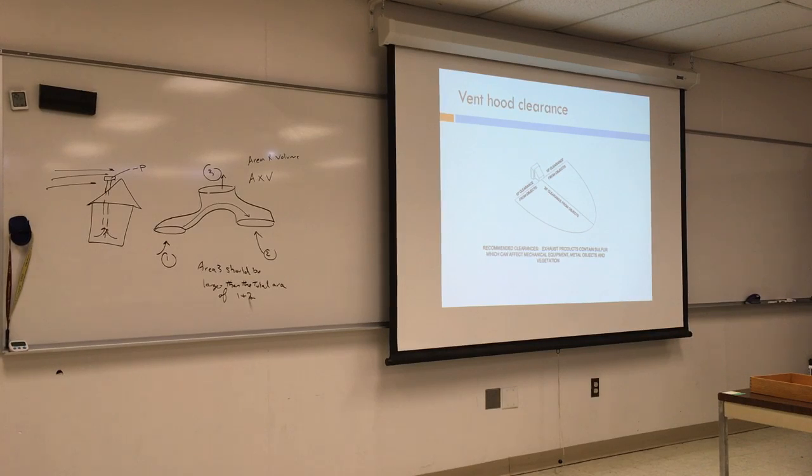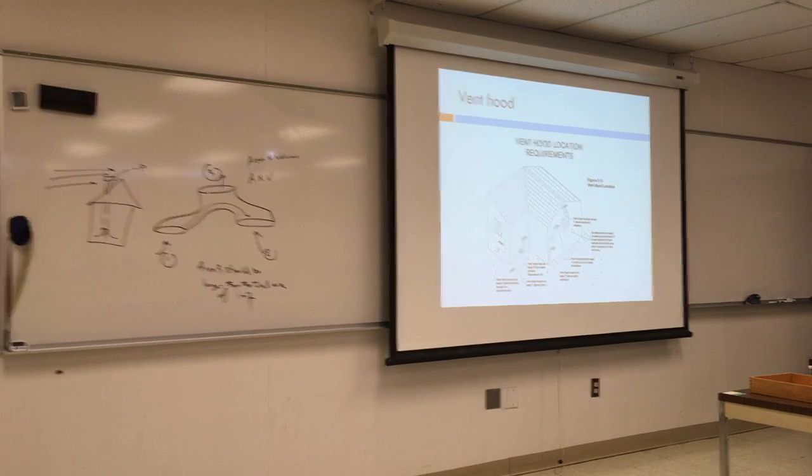Can you go back one page? Yeah, and from inside corner, we have only 3 feet. But it's not clearance, it's corner. It requires at least 3 feet from inside corner, recommended 10 feet. If you look closely here, this is your recommendation here, and this is the minimum. And it's good to refer to this page whenever you are doing installation.